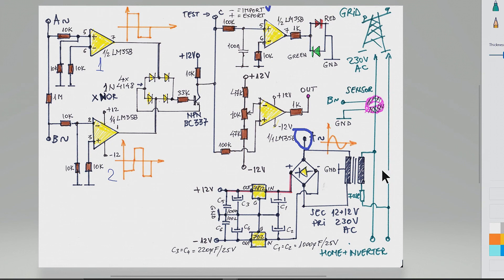Here we're going to have either a minus voltage - that means import, so the current is going from the mains to the house, and that includes the power delivered by the inverter. Or we have export, so that means the inverter is pushing current toward the grid, and that will be a plus voltage here in point C.